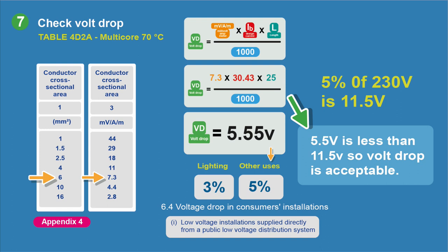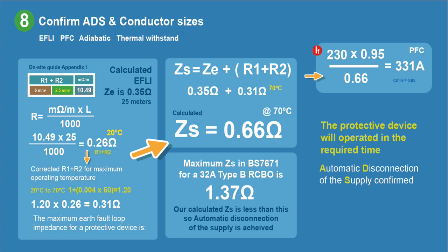There is a preliminary check you could do right at the beginning to see if the cable might be suitable — I'll show that at the end. So that's how we check our volt drop. Next we can consider our earth fault loop impedance and confirm whether automatic disconnection of the supply will be achieved. This is the calculated method — obviously the circuit's not installed yet so we can't test it. Our formula for Zs is Ze plus R1 plus R2.